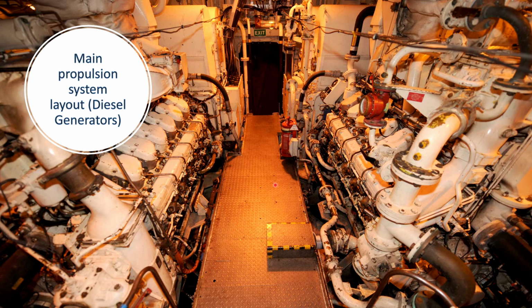In an emergency, the two systems can be cross-connected. The downstairs diesels have their own built-in gear-driven pumps which suck water directly from the sea, but they can be connected to the low-pressure saltwater system in an emergency. Thus, in the event of a total electrical failure on the ship, you would have to start your downstairs diesel engines first, because you wouldn't be able to power the low-pressure saltwater system to power up your upstairs diesels — although you could still run them for a few minutes without any cooling, so you probably could do it if you absolutely had to.